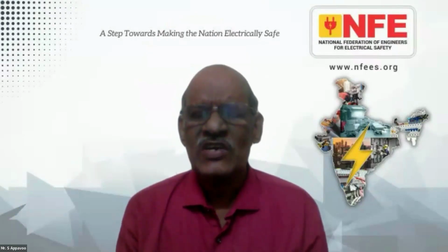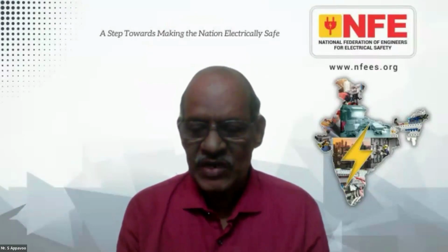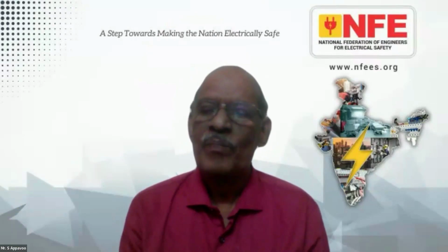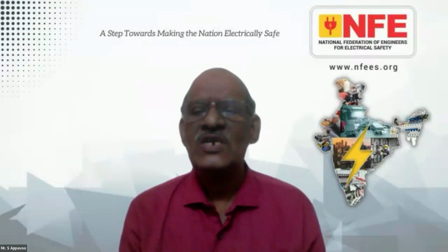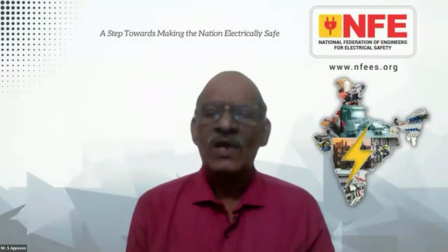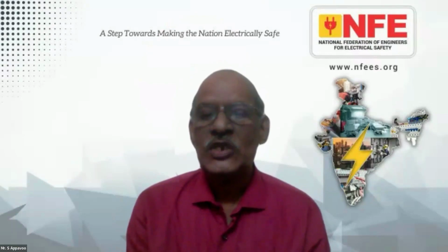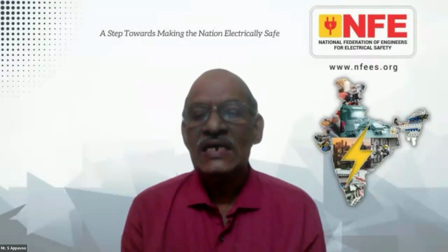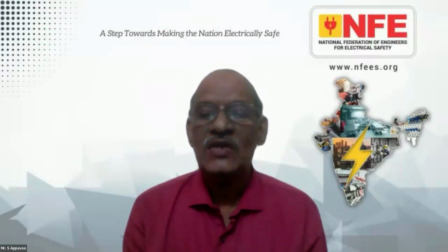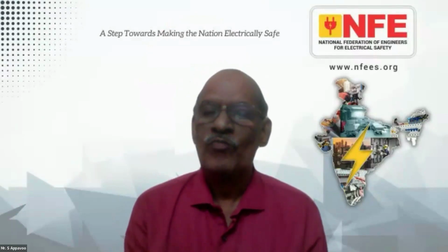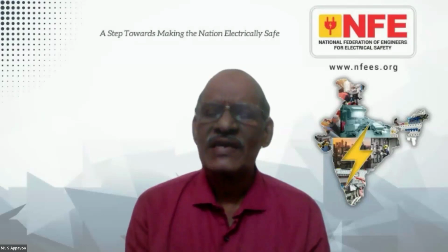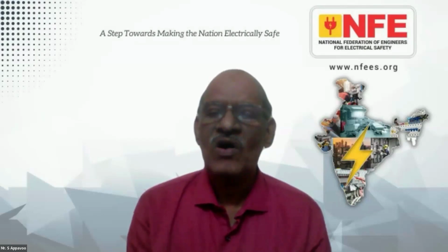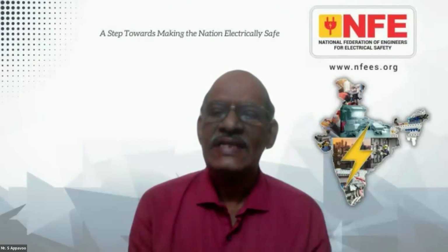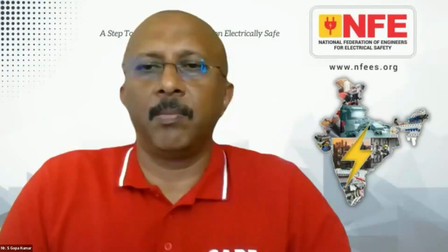The regulation prescribes the pole earthing at frequent intervals, for example, 3 per kilometer. And another thing, earth electrodes are to be insisted as per regulation. It should be provided for every consumer. So all the pole earthing, earth electrodes and your distribution transformer earthing will constitute an overall effective earthing system with the TNC connection. It is sufficient if you provide practically a grid, in small locations also it is possible. The integrity of connection should be maintained.